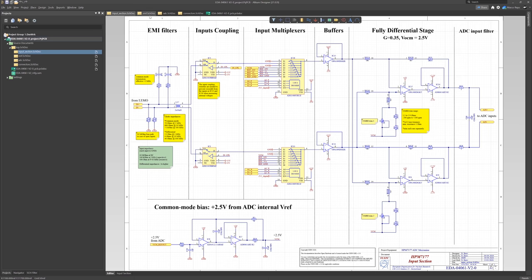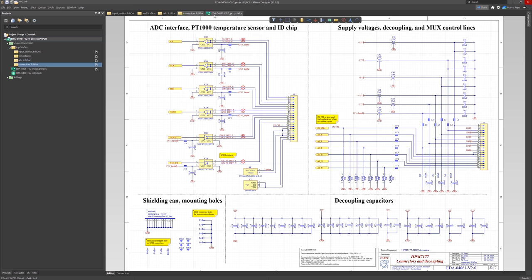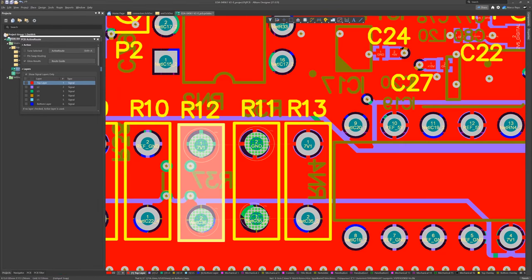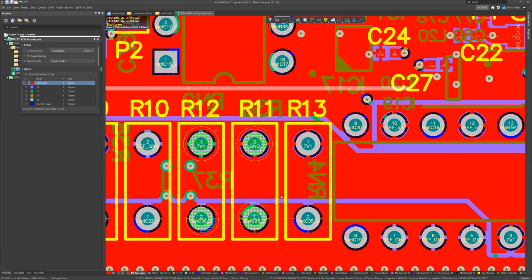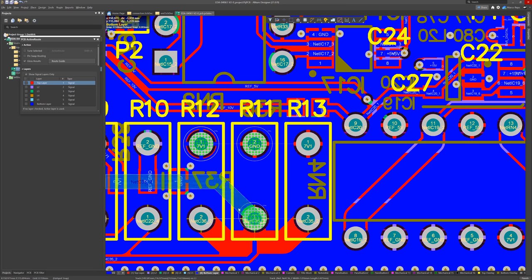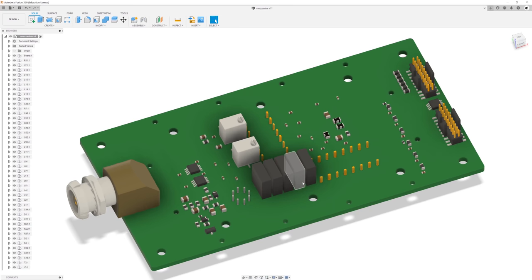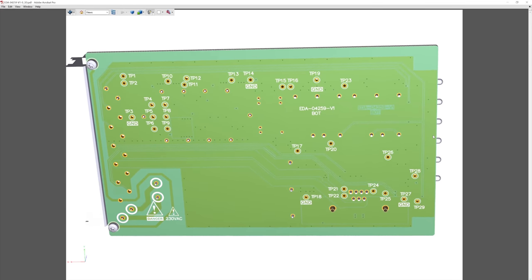I also love the fact that this design, except for a handful of custom resistors, uses only off the shelf components, meaning that everybody with a bit of determination could replicate it. What I'm going to do is replicate it, swapping around the LTZ supporting precision resistors a little bit. I want R11 and R13 to be right next to each other, so that I could use two separate resistors or a network diagonally across the two, which is cheaper and has much better ratio stability. But let's not get ahead of ourselves too far.